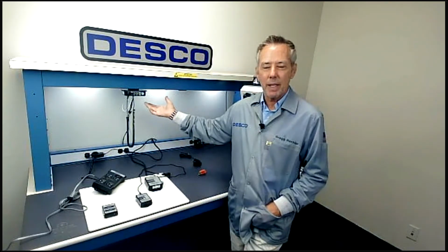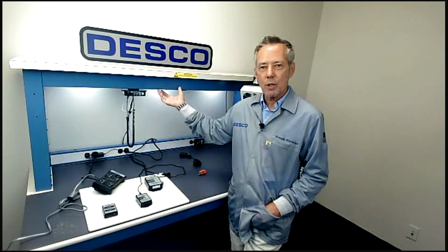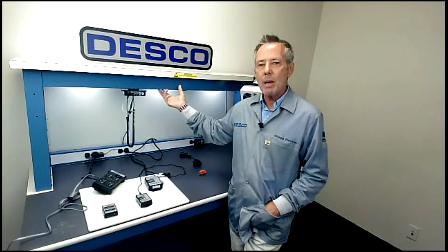There are third-party outside sources that can calibrate our monitors. Many of those companies use our limit comparators to do that. So you could do it in-house, you could do it outside, you can send them back. But with our limit comparator, the nice thing is I don't have to demount the monitor, especially if they're screwed to the workstation. The limit comparator is inexpensive, and it's a great way to save you a lot of time and money on calibration costs.